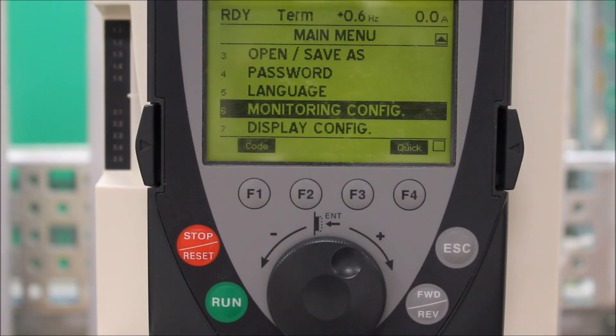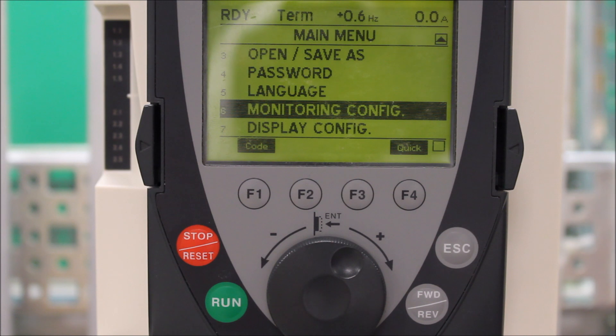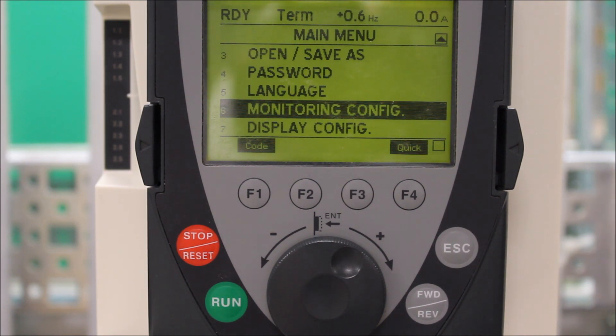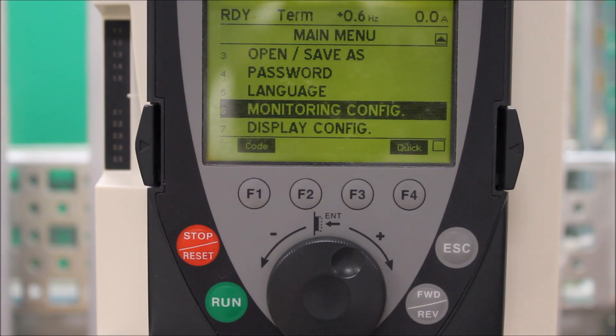In this video, we're going to talk about how to set your ATV61 and ATV71 drives keypad to show you your motor RPM instead of frequency.